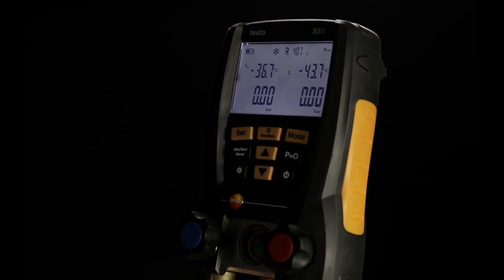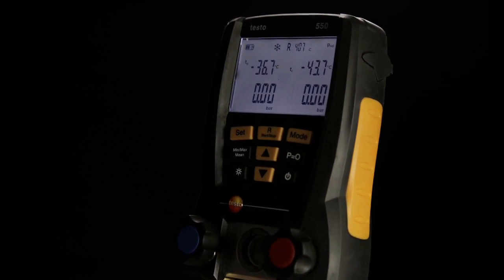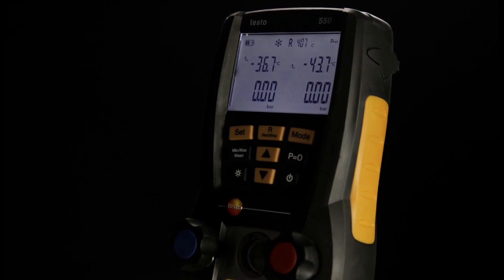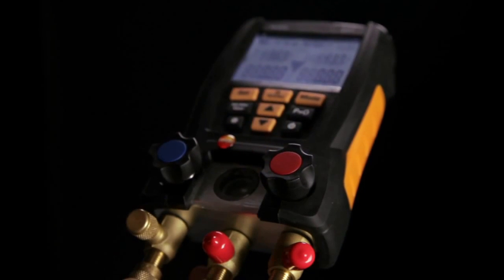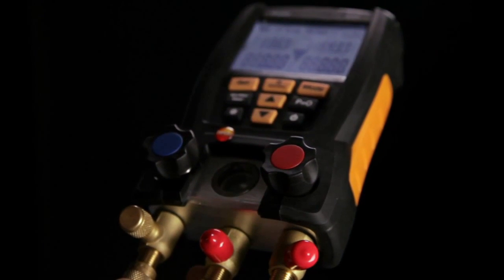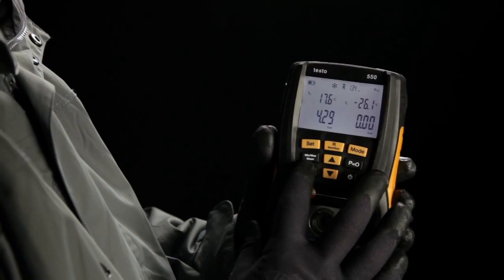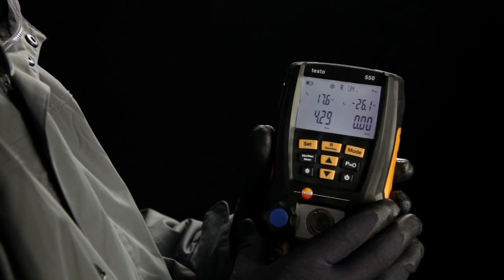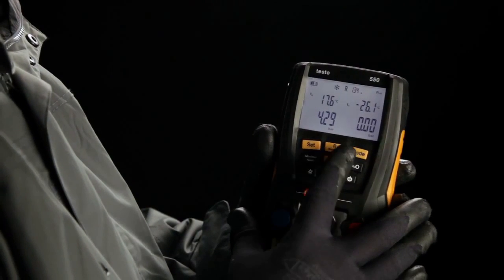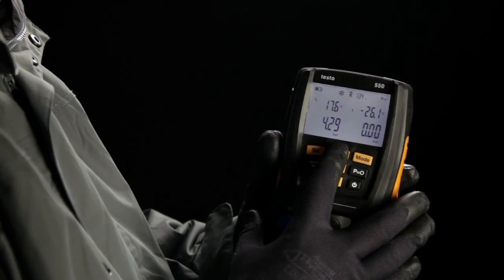You now need only one instrument to carry out your work. In addition to pressure, temperature, superheating and subcooling, the Testo 550 can be used for evacuation and temperature compensated tightness testing. The selection of 39 preset refrigerants increases convenience even more.